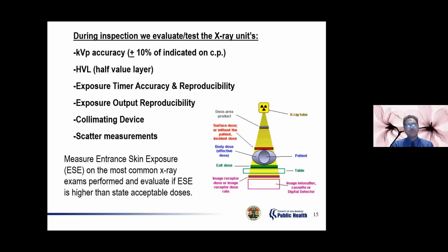Exposure time, accuracy, and reproducibility. We want to make sure that when you're putting 0.2 seconds in there, you're getting 0.2 seconds, not 1 second. Reproducibility is basically, if I shoot 3 exposures at 80 kVp at 50 mAs, I should get the same exposure 3 times at that technique.